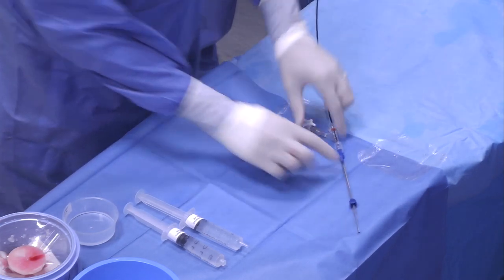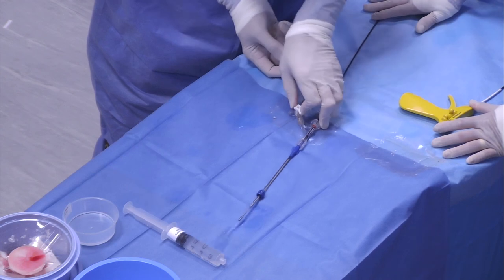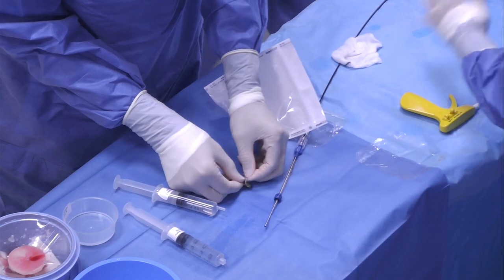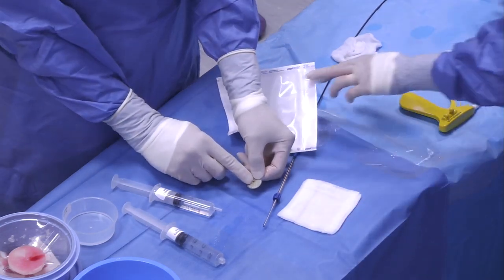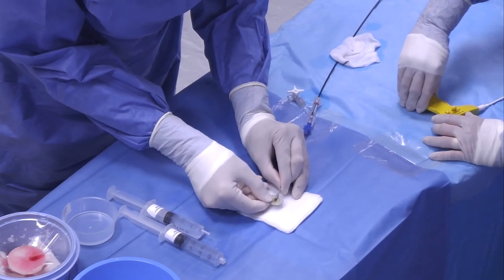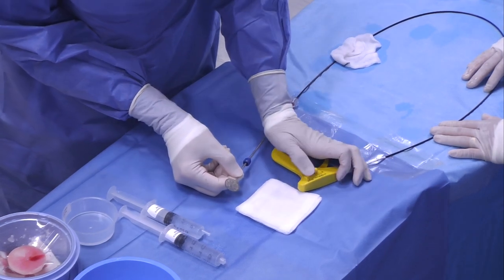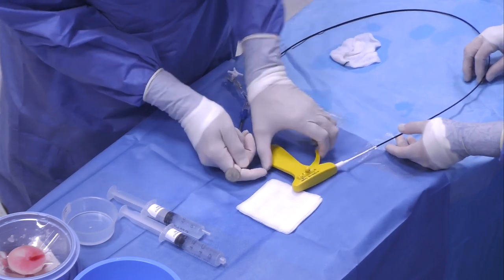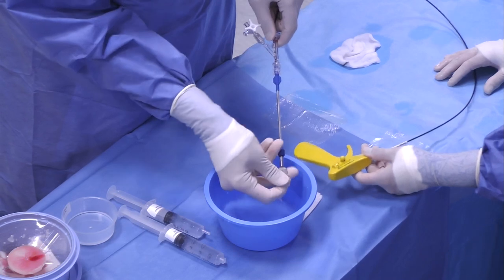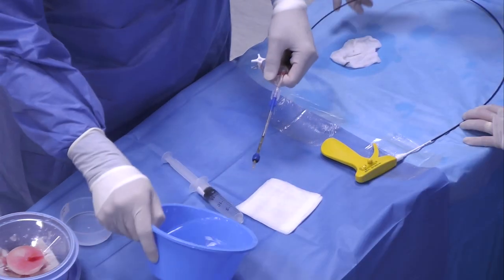The delivery system from OccluTech — flushed to wet it slightly. The standard device has a very narrow waist with one ball to catch onto. Firing the gun opens a pair of forceps to catch the device — it's caught and rotating nicely. Locking it so it can't be released by accident. The device is then taken underwater; stretching it while pulling it in to check it comes out in a decent shape, which it has. The whole sheath is underwater during loading, then flushing out with a full syringe load to ensure absolutely no bubbles.